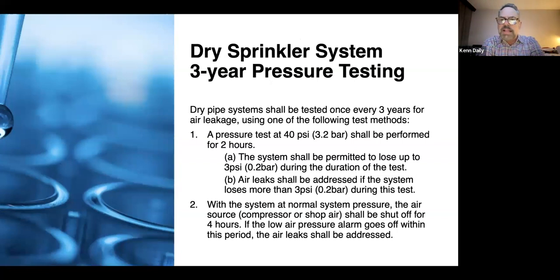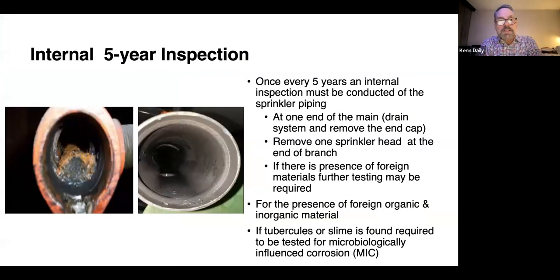3-year pressure test, again, making sure you're getting that documented by your company. Pump it up 40 pounds, 2 hours. You lose more than 3 pounds in 2 hours, you have to begin finding pinhole leaks and have it retested. Again, testing maintenance is always a passing test. So if you fail a test, that doesn't count. You actually have to fix whatever, and then have it retested to make sure it's working. This is that 5-year internal inspection.